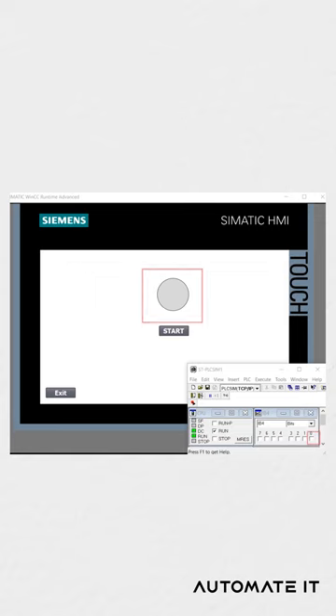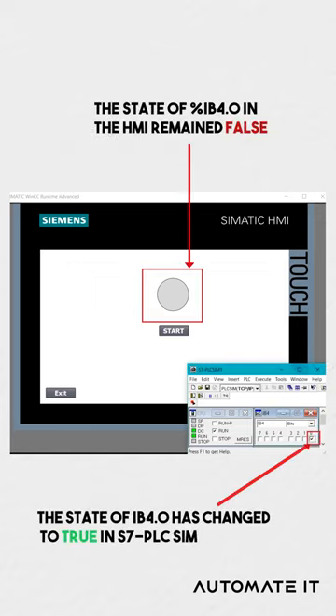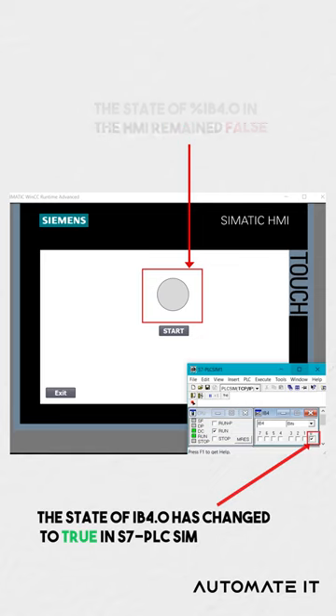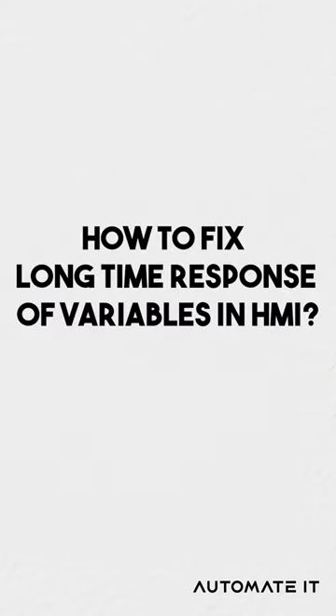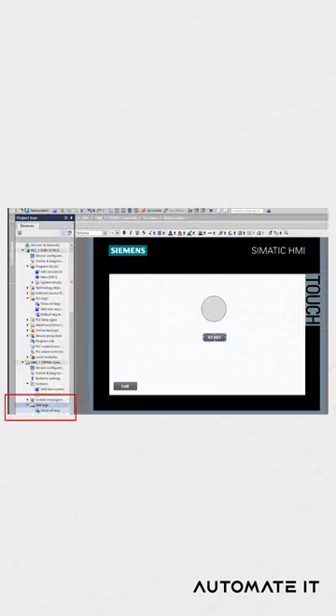If your variable on the HMI takes a long time to change its state, it is likely due to the cycle time. Here is how to fix it.